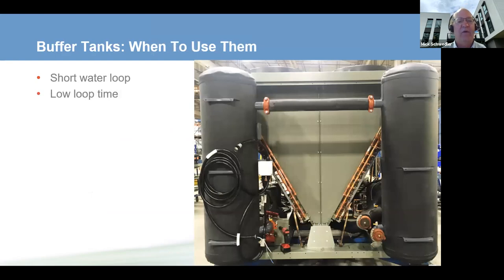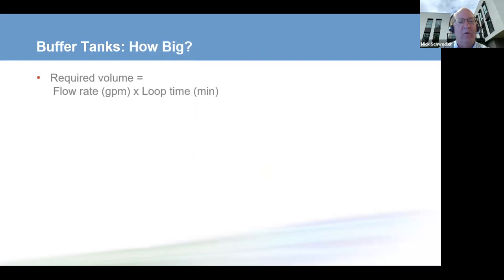This can happen if we have a short water loop. Say we have an air-cooled chiller outside a school and the air handlers are right inside the wall. There isn't much system water volume. The water gets back to the chiller very quickly and we have a low loop time. So how big? Well, the required volume in your system is going to be equal to the flow rate times whatever the manufacturer tells you their required loop time is. So that might be 1, 2, or 4, or 5 for some small chillers.